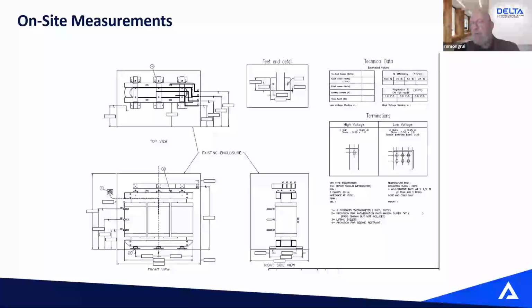Usually, the first time you have to do a retrofit, we can provide assistance, either people from Intralec, even people from Delta can go on site and assist you with doing the full measurement of the process. That's probably the most critical portion of the project, to make sure that we have accurate measures of the existing transformer and existing equipment. Not having the right information will result in not having the right product.